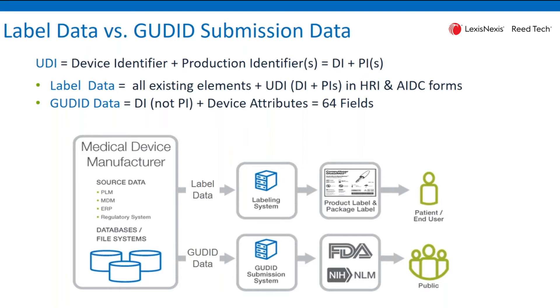The other data flow, which is on the lower row, is brand new and has not been implemented in the past. So when UDI requires it, you'll need to create a procedure, pathway, and means to collect UDI information, build the particular messaging, and send it to the regulatory bodies — in this particular sample, the FDA — so that you do meet the regulatory requirements.